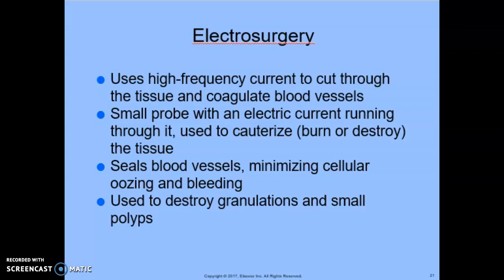So again, if that switch is on and you're passing back and forth, if he asks you to hold for a second while he gets a better view or is using a retractor to get in better, it's still important that you handle it as if it's always active, because if that switch is on or his foot happens to still be on that foot pedal, there is an electrical current running through it.